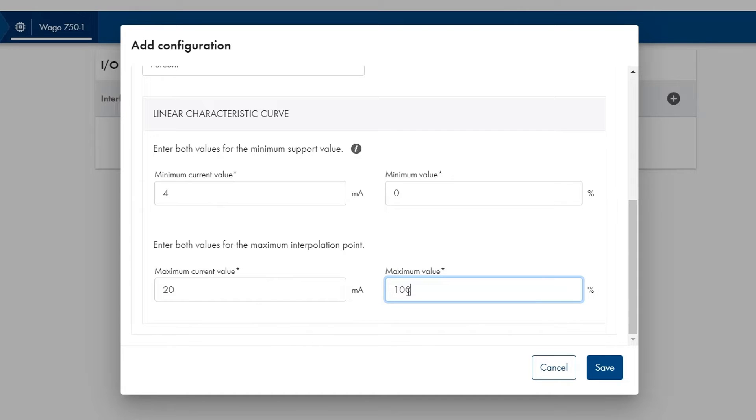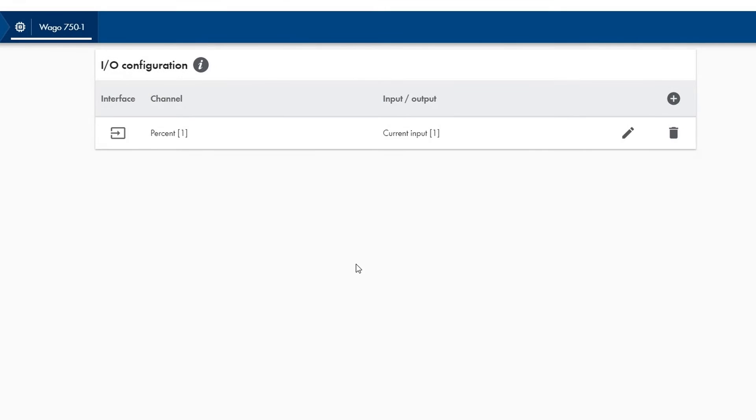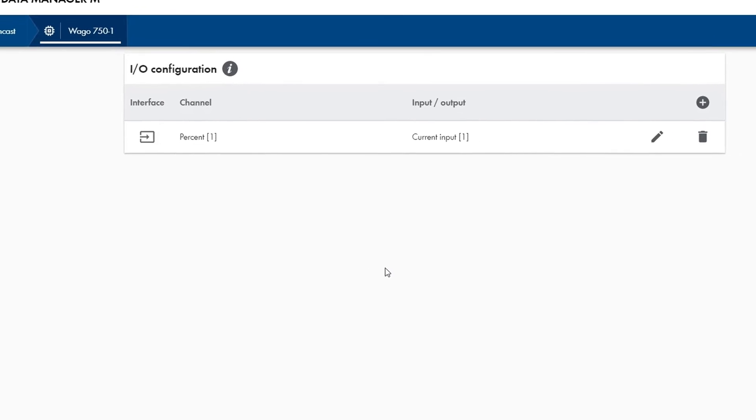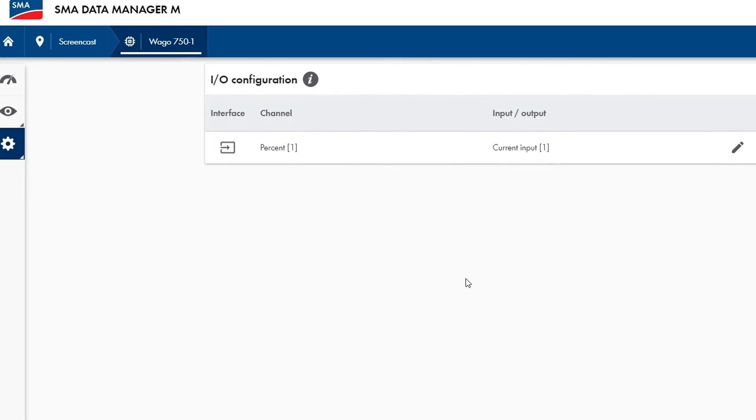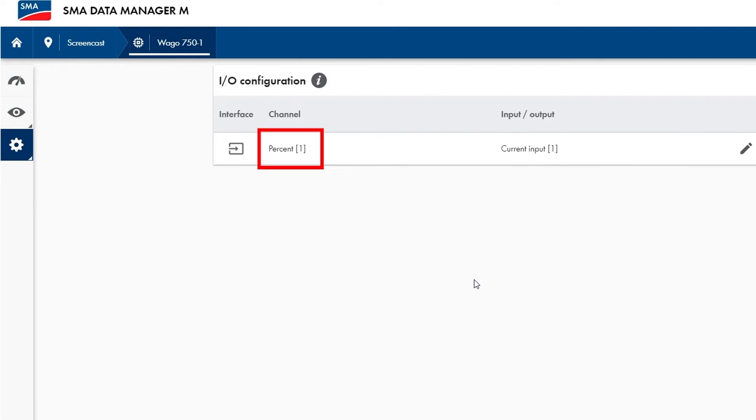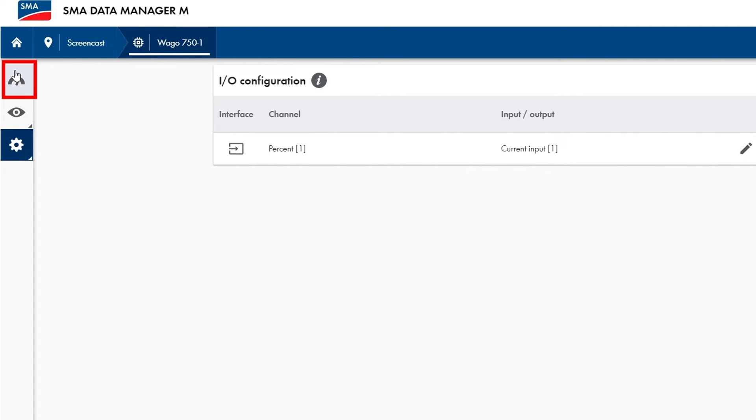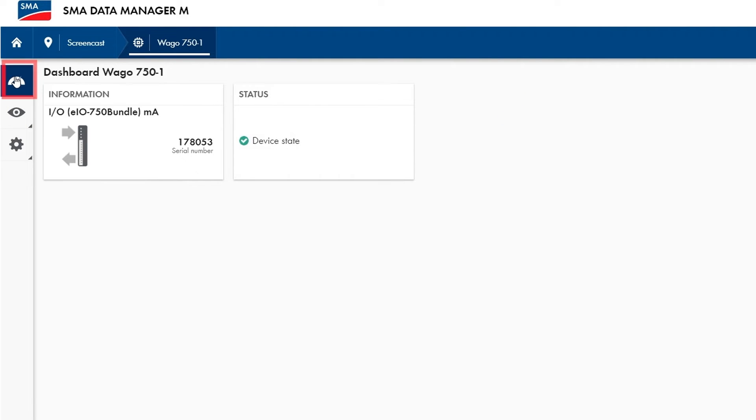An important hint at this stage: for the configuration it is necessary that a valid signal of 4 to 20 milliamps is already connected. Once I have completed this setting I click on save. In the I.O. configuration overview screen I can see that the Modbus configuration is now displayed in percent. I can also see in the dashboard that the device status is OK.